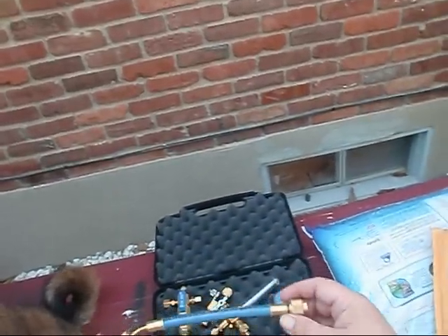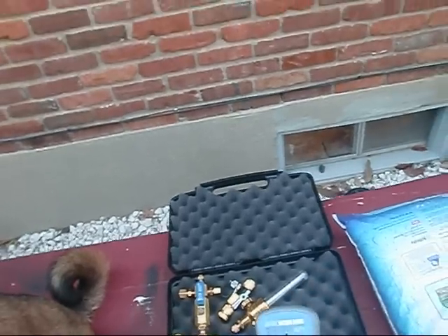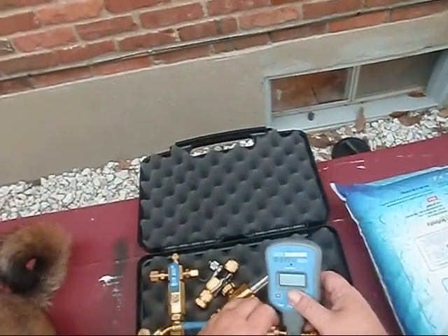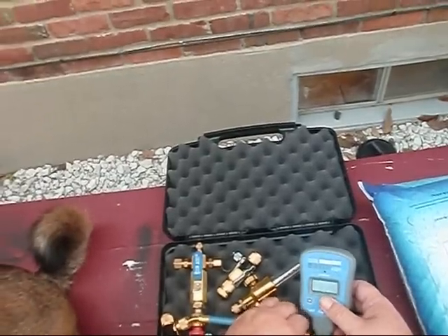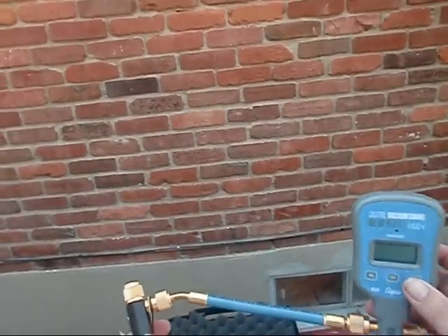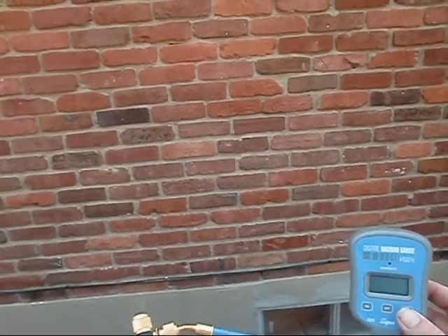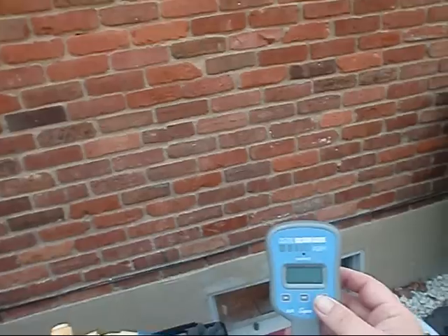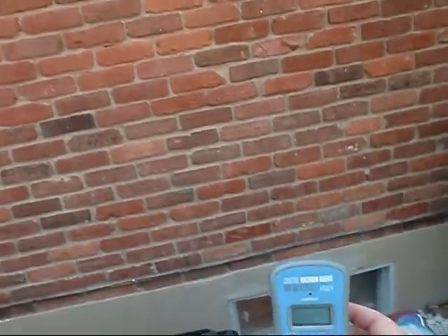He said we'll make you a hose for this one — it's only going to be six inches long, we're really not concerned about that. So I'll actually be able to uncap my micron gauge here and screw it directly in here like so. Now guys, we're ready to rock. I got the official Appion going directly into my suction line port. I'll have the Schrader valve removed from the valve itself, with a very, very short run from my micron gauge to my Appion Schrader core remover. We should start pulling some wicked freaking vacuums with this.